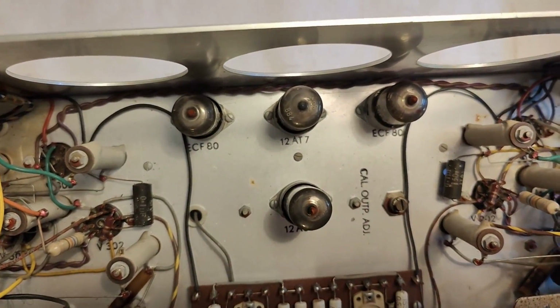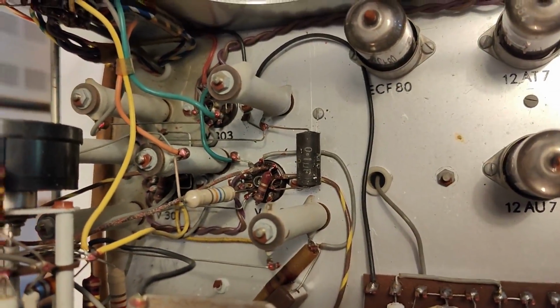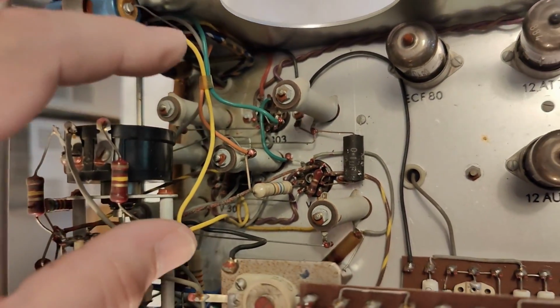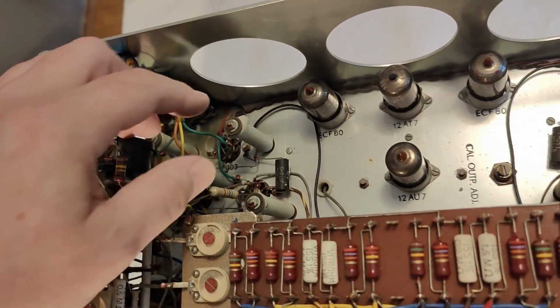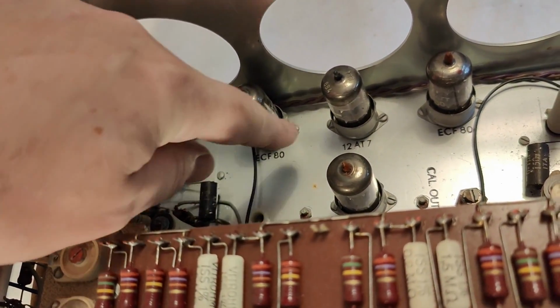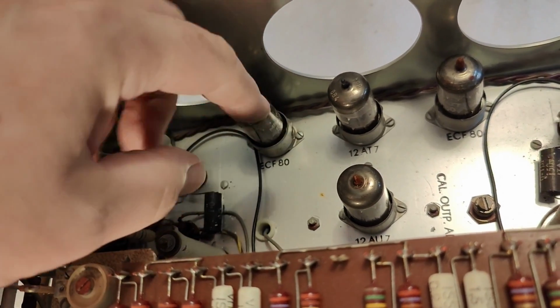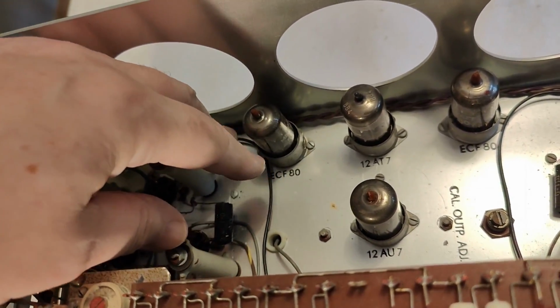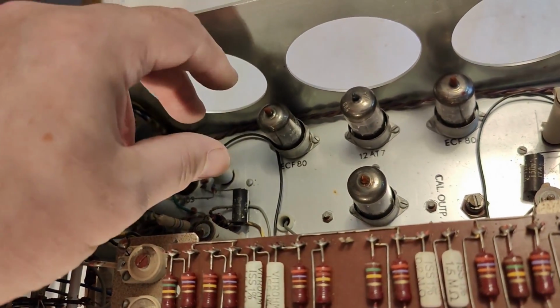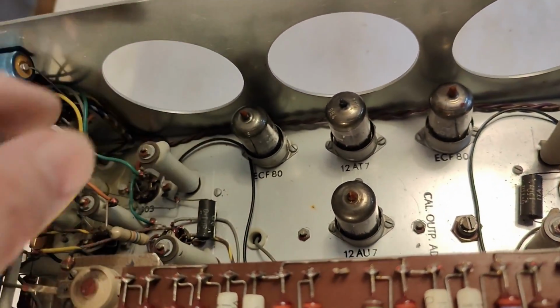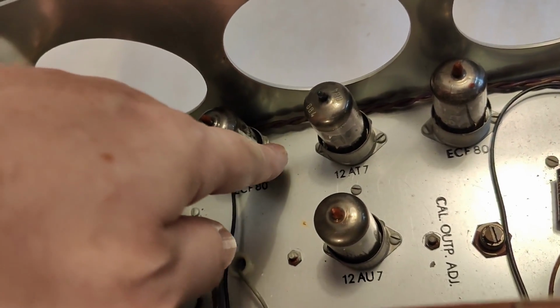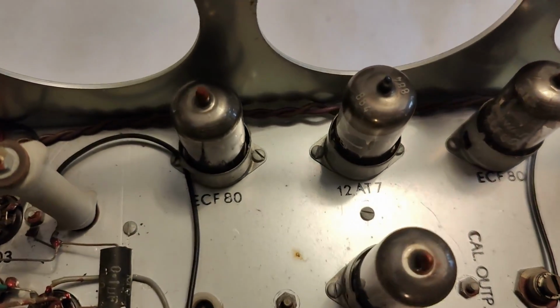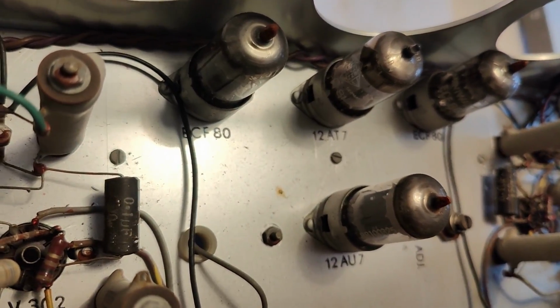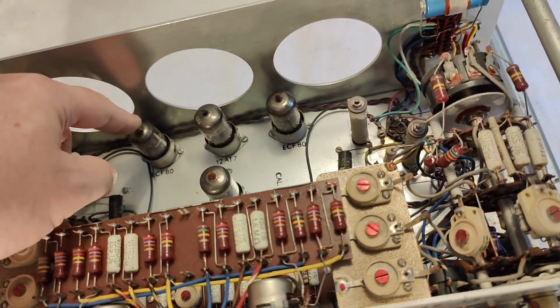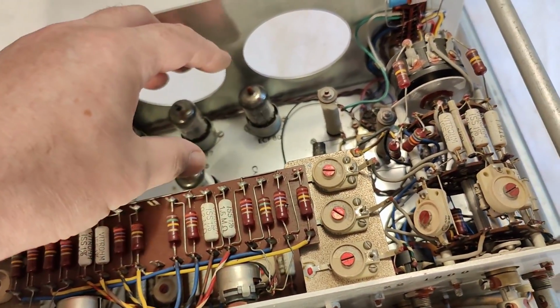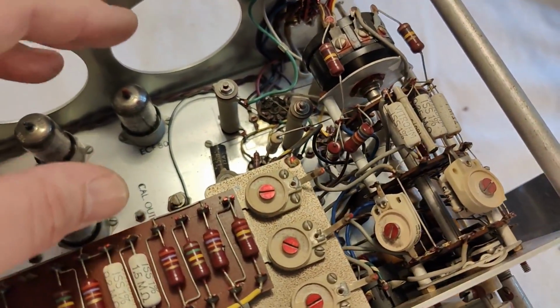Some tubes point up, and the sockets down there point down, and that is of course to create isolation, because the outer part in many of those tubes will be anode, so it's a sensitive part of the tube. And instead of needing to put those isolation metal tops on, and you can see those sockets here, they actually support the isolation tops, but this will also make the tube run much hotter. So you don't really want to use them if you can avoid it.